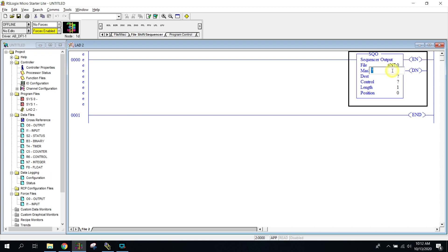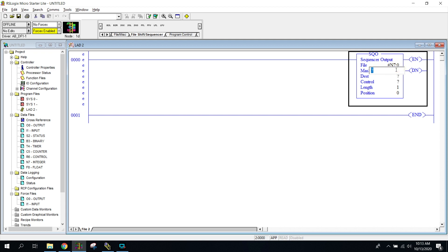The next parameter, which is probably the most difficult one, is the mask. The mask tells us how much of the word we're going to be moving to the destination. If N7 has 16 digits in it, are we going to move all 16 digits of that word over into the destination? We use a hexadecimal number to determine that — whether it moves all of the information from N7 or just one bit. What we're going to use is a mask of 0FFFFH. Make sure it's a zero, not the letter O, or you'll have problems.